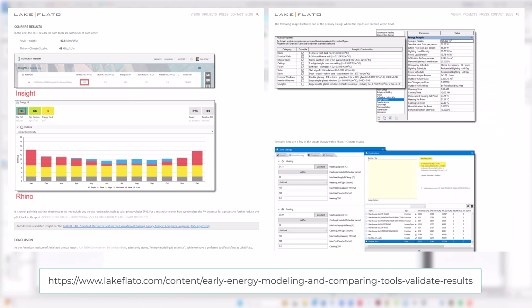By the way, I don't think I mentioned this, but Insight currently uses DOE 2.2. In the future, and I'm part of some beta, it will use EnergyPlus for basic systems like this. The results should generally be the same. I have a blog post I think I've mentioned before on the Lake Flato blog that compares this with Climate Studio's tool that uses EnergyPlus, and I carefully matched all the inputs and everything was super close. But in the future, the EnergyPlus one will also have a few more advanced HVAC systems, like a VRF with a DOAS system to be able to choose from, which is really great.